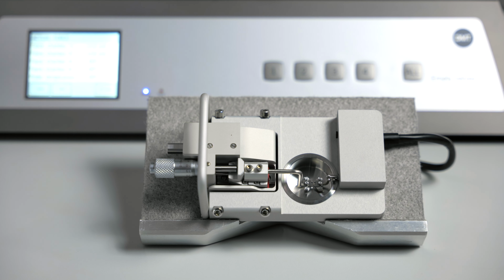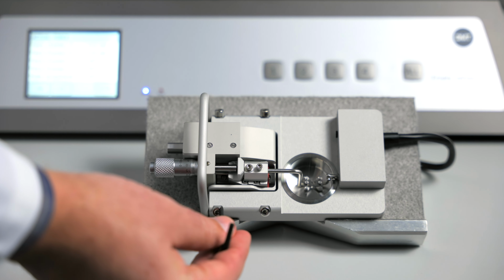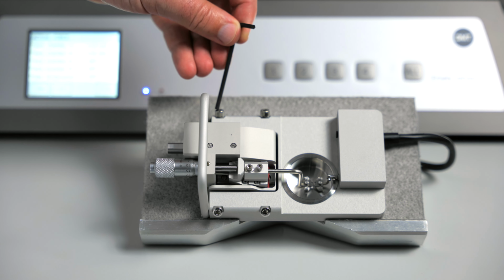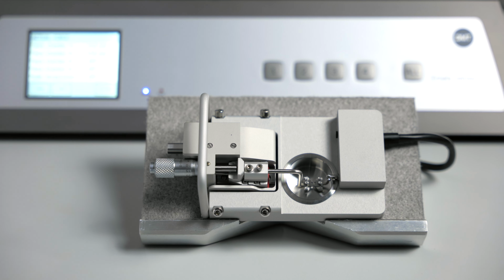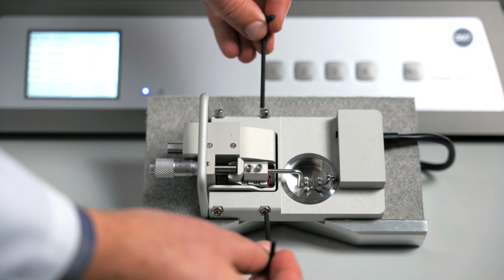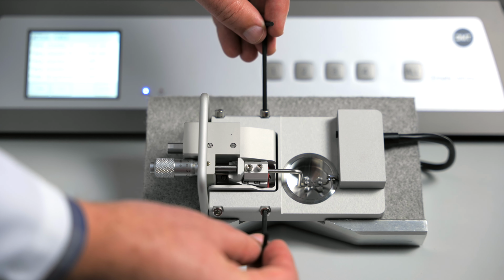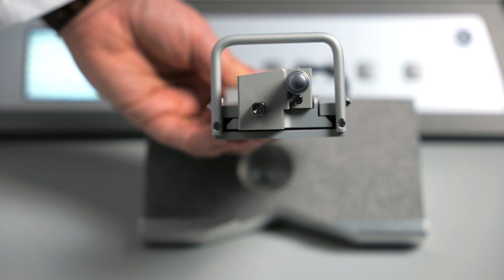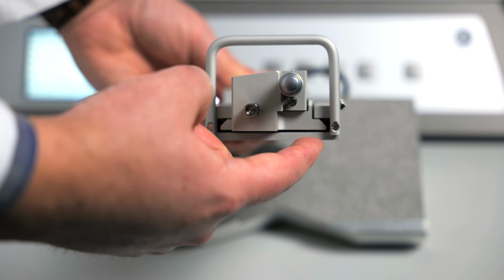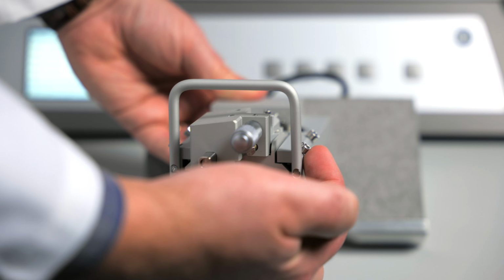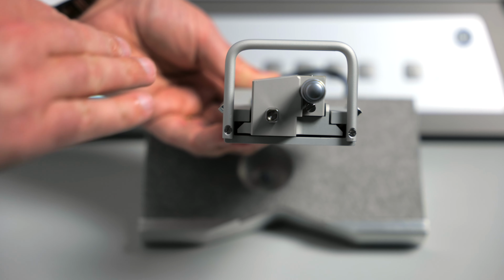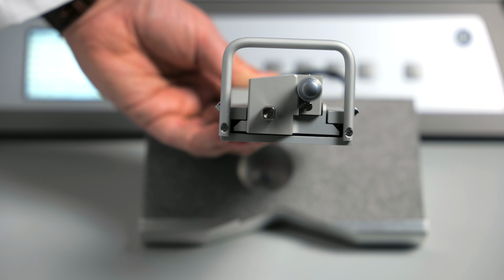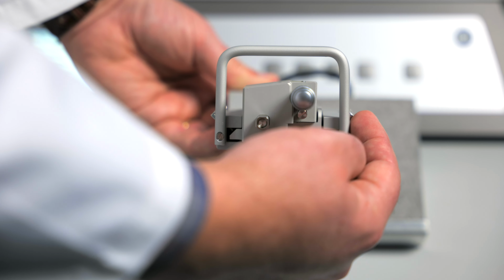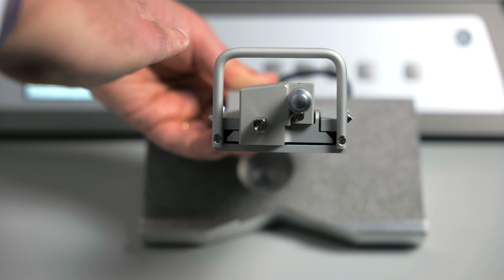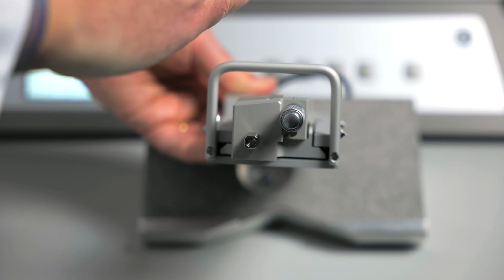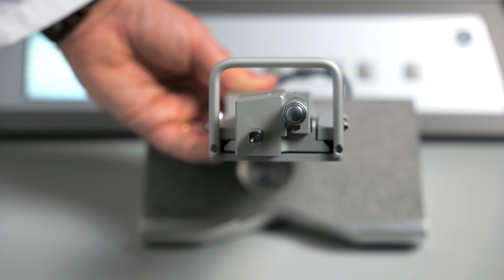In order to make your fine adjustments, you will use your Allen key and the 4 positioning screws in order to get the exact right alignment. If you have 2 Allen keys, you can adjust 2 at the same time, which will make it easier. You can see that the positioner and the motor are separate from the chamber itself. Therefore, when you press on any of these screws, it is adjusting that entire plate in 2 directions. So if you tighten this back right screw, it will bring the front of the chamber and your jaw up and to the right. Keep that in mind when making your fine adjustments.